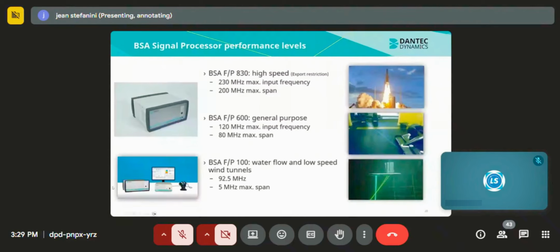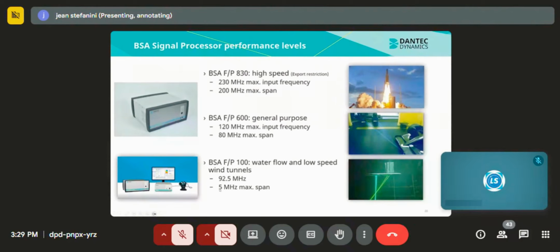So you can see this is a general configuration of an LDA system. You have a laser in this box. You have a transmitting probe using fiber optics that is going to transmit the light. The light will be collected by the same probe and then transferred to this unit, that we call the signal processor, that will measure the frequency of the signal. There is a direct linear relation between the frequency and the optical configuration. We have different models that go from very low speed for water flow to very high speed, up to supersonic flow or even more than 1,000 meters per second.